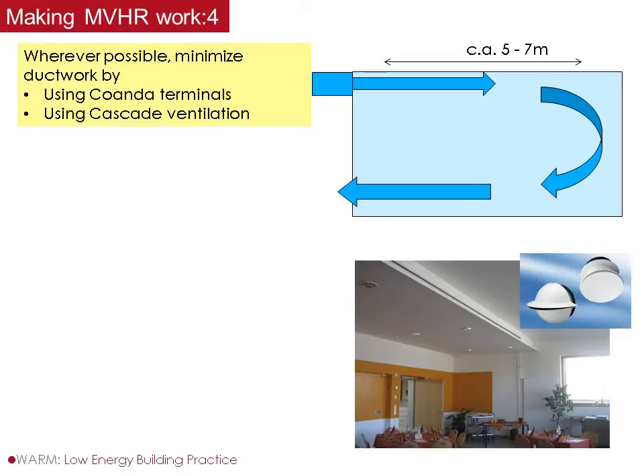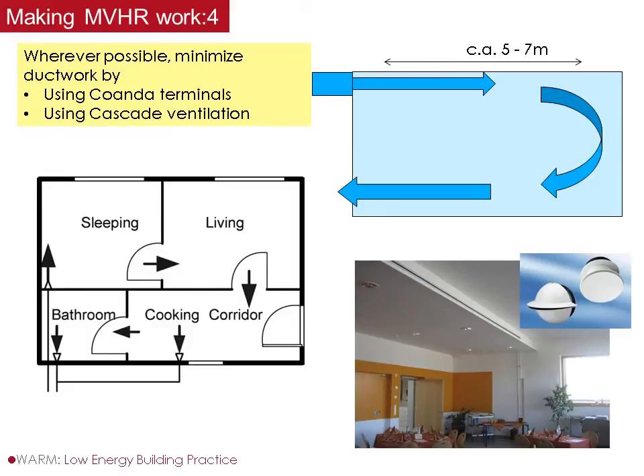The other trick is a thing called cascade ventilation. Relatively new in the Passive House world, but increasing attention is coming to it. What it's about is very simple: rather than extracting every wet space and supplying every dry space, you try and cascade them down. Here's an example: a flat with one inlet into the sleeping area. It comes through the door, through the gaps, into the living area, through the corridor. There's one extract in the kitchen and one extract in the bathroom. So you've only got 3 terminals, very little ductwork for the whole flat.